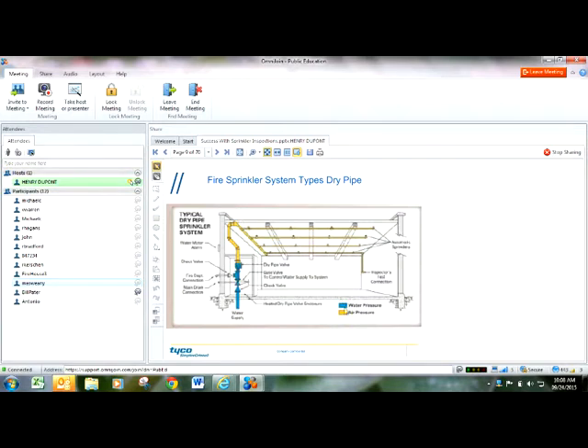On a dry pipe sprinkler system, you have to be able to prove that you can get water to this most remote inspector's test connection within 60 seconds. And we're going to talk a little bit about pipe corrosion and how obstructions can slow that time down, but that's a few slides ahead. So those are the two major types of sprinkler systems. If anybody has questions about the difference in the two, chime in at any time.